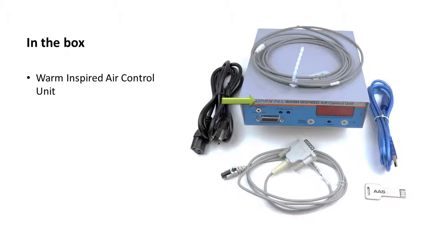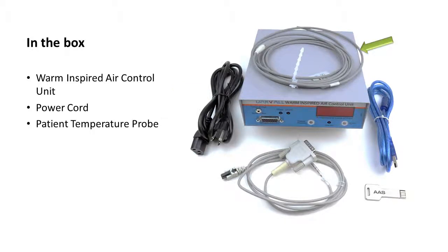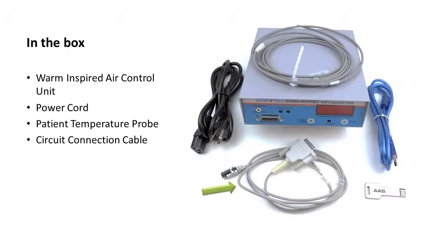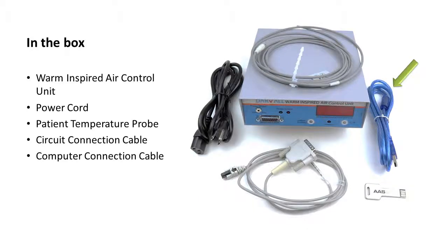The warm inspired air control unit, the power cord, the patient temperature probe. Although your vital signs monitor may also monitor temperature, use this one when using the heated circuit. This temperature probe is part of the heated circuit's biofeedback loop that protects the patient from overheating. The circuit connection cable, the computer connection cable.